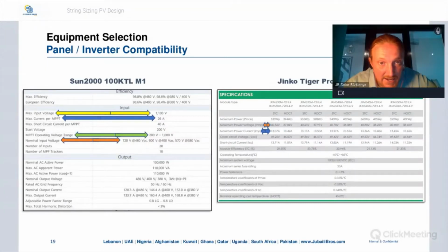And on the right side, again, the orange arrow, it's the maximum power voltage. So you should pay attention to that maximum power voltage, because that means at the peak sunlight, that's the voltage your panel will generate. Now also look at the yellow on the left. That's the maximum input voltage. It says 1,100 volts. And then the green arrow is the MPPT operating voltage range, 200 volts to 1,000 volts.